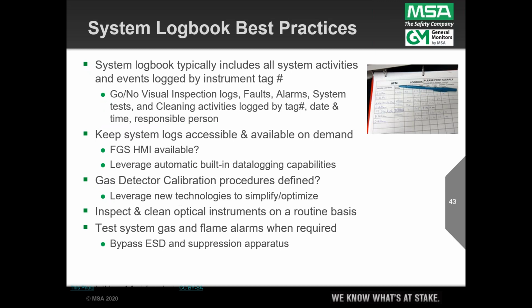A fire and gas system should have a logbook. This actually complies with ANSI/ISA and NFPA 72, where we have all of our faults, all of our alarms, our tests, our cleaning activities, logged by device tag, date, and who. I love the new HMIs on some of the new systems, because in the old days we had a three-ring notebook or a spiral notebook. Now we can have an automated graphic user interface from the logic solver. If we lose the logbook, we've got a copy automatically populated by the logic solver, which I really like.